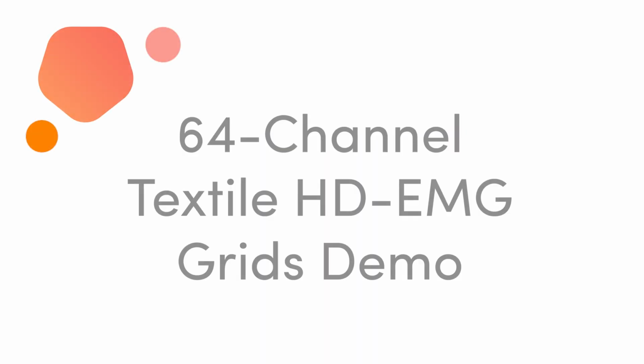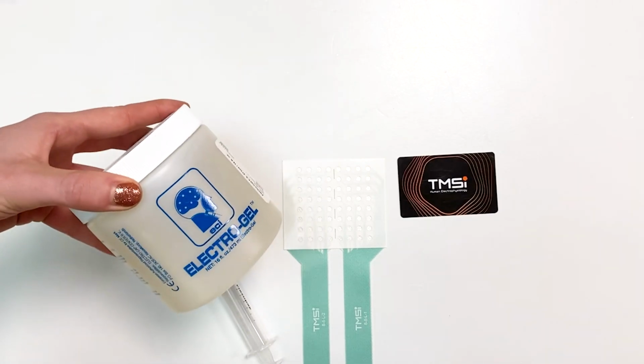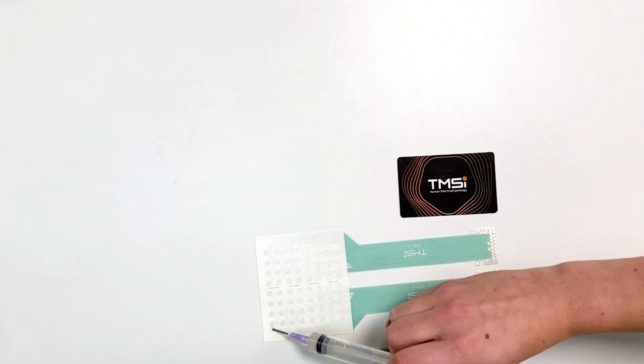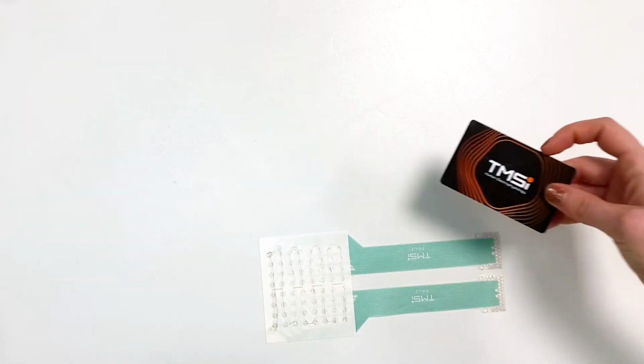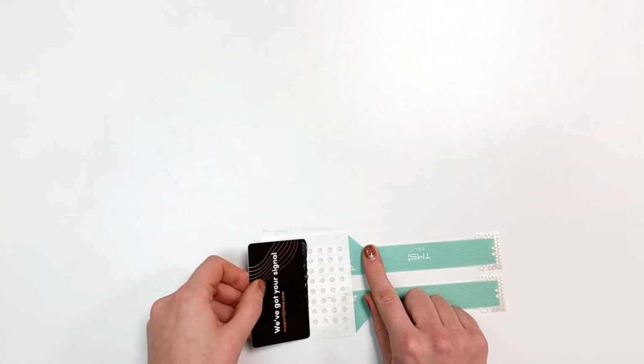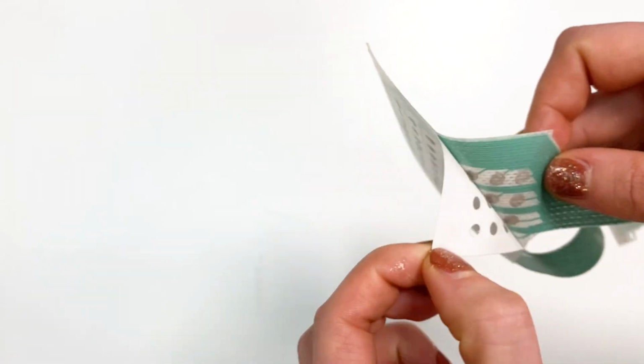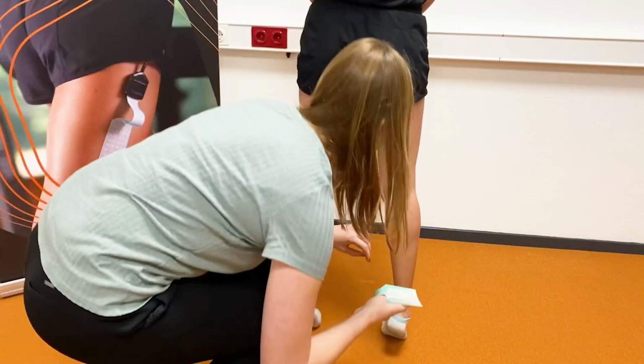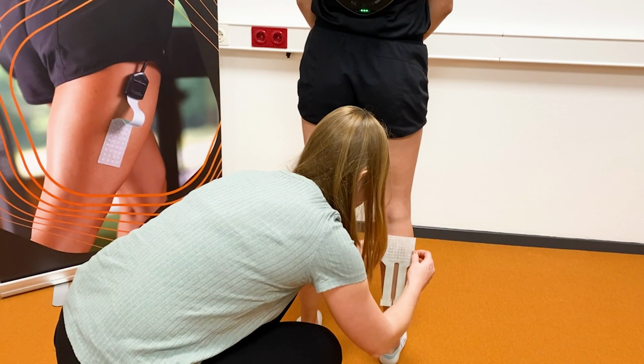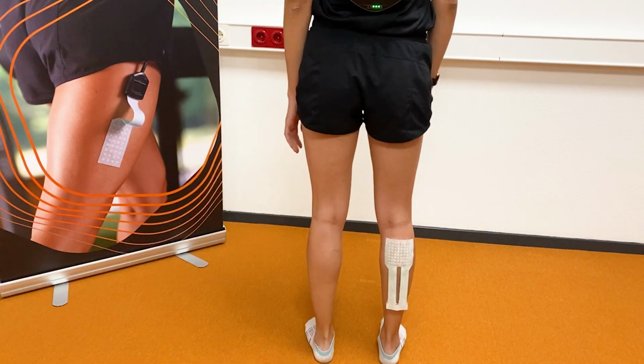In this video, we will show you a short demo of our 64-channel high-density EMG grids. Start by applying gel on the grid and spreading it with the gel applicator card. When all electrodes are gelled, remove the top layer of the double adhesive and place the grid on the prepared skin. Make sure the skin is prepared beforehand.